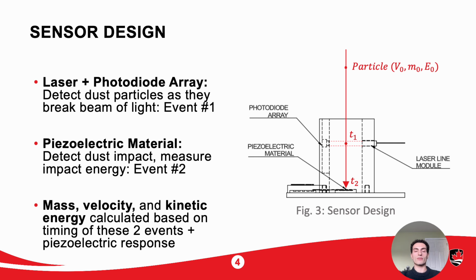The sensor is composed of two main parts, the laser/photodiode beam break and the piezoelectric detector. Incoming particles will travel into the detection chamber and trigger the laser beam break. This is event number 1. At a fixed distance from the laser beam, the particle will impact a piezoelectric detector. This is event number 2.